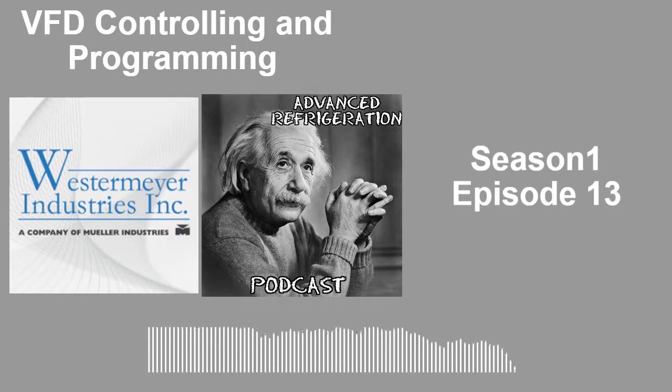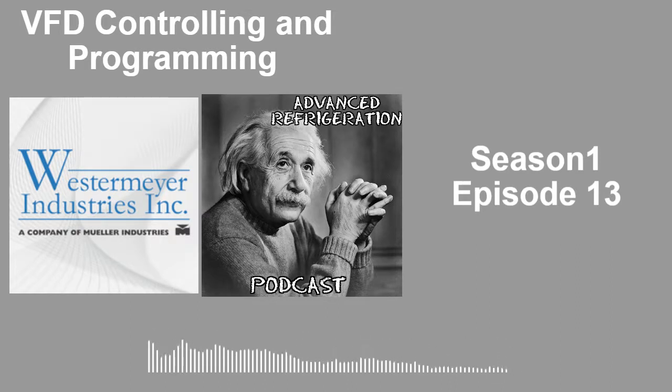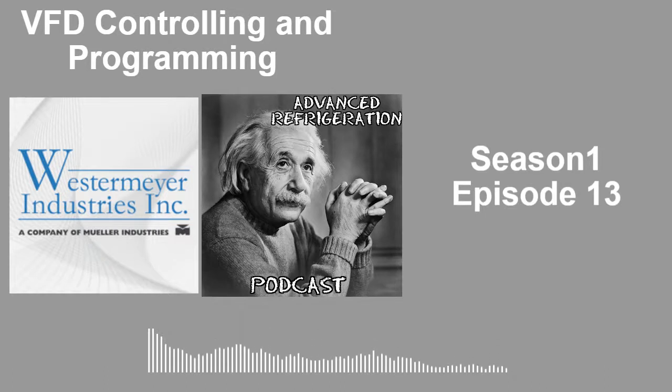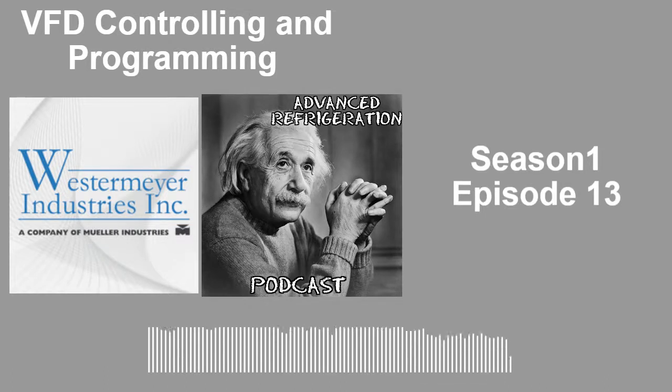Sometimes, RDM right now, in conjunction with Zero Zone, what they're doing is, I don't know enough about the RDM programming, but I know they are setting a 0 to 10 volt signal out to their stuff. But what they do is they actually use a converter board, which takes the 0 to 10 and reverses it, and sends it out 10 to 0. So in case something happens with the analog out, it's still sending out that voltage to those motors to run at a certain hertz.